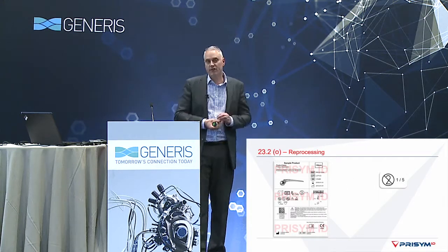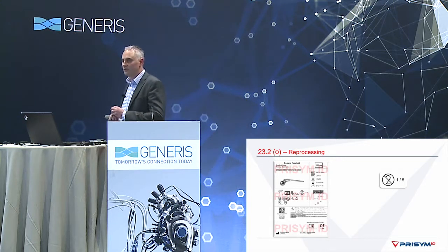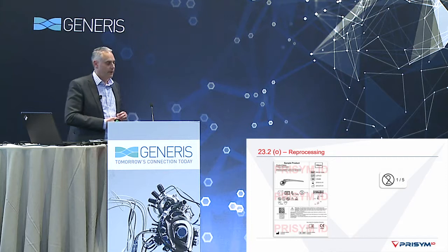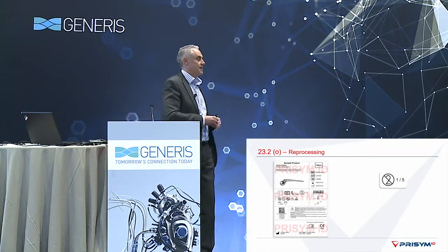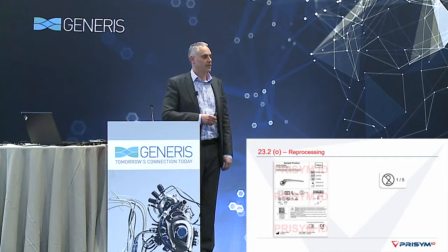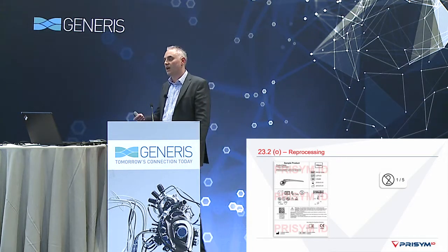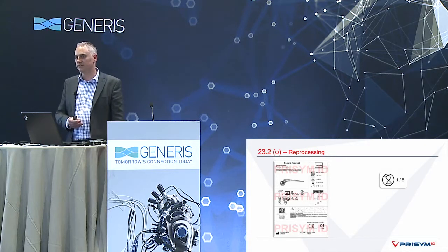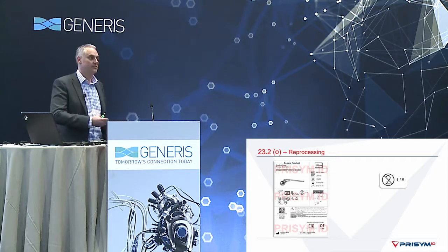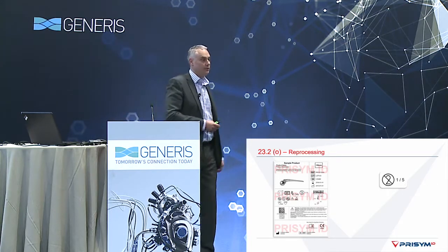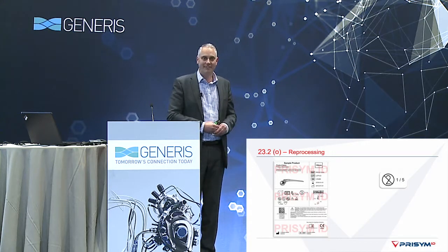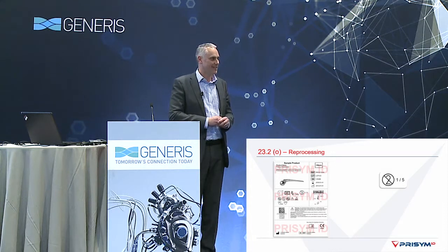Reprocessing, out of interest. Anyone in the room have medical devices that they recycle or reprocess? Yeah, so the EU MDR has got a lot more regulatory requirements around this. You must have the symbol on there saying whether your device can be reused, recycled, reprocessed, as well as saying how many times it can be recycled, reprocessed, if relevant. Now, of course, the impact of this is more than just a nice little symbol on your label. The impact is you've got to have the management systems that are tracking at a device level how many times you've recycled or reprocessed that.